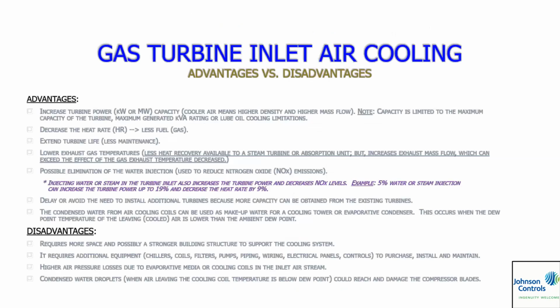So advantages versus disadvantages. Of course, the advantages I've talked about, but here's a good summary page. You increase the turbine power, get more capacity with cooler air. You decrease the heat rate, less fuel. You extend the turbine life. Well, what do you think happens? You got colder air in, right? I mean, all motors, any kind of motor or rotating equipment, as you gas turbine guys know, and even you ASME guys know, if you can cool that air in a motor or a turbine, it lengthens the service life. So you got a side benefit to that.